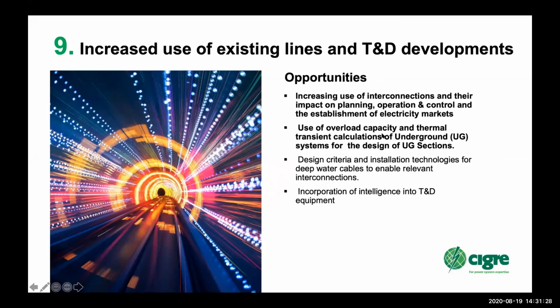Opportunities include increased use of interconnections, impacts on planning, operation, control, and establishment of electricity markets. And then again, use of overload capability, not only on overhead lines but on underground cables and systems, is one of the areas where, due to variation in load, it's important to have robust networks that can handle quite high variations in load requirements. Overhead lines are quite resilient to that, and you can use real-time monitoring and other devices to actually raise your overhead line thermal rating. But underground cables and other devices on the system may not be so resilient. So you're looking at underground systems, transformers, breakers, and so on.